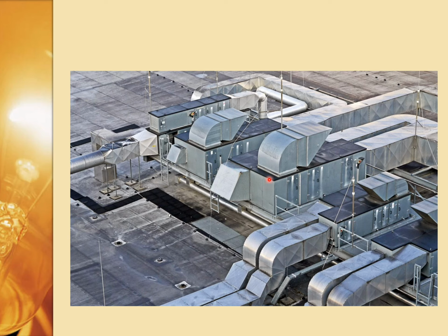So when you've got the economizer in these units open up and you're sucking in nothing but 100% outside air, you don't want to overpressurize the building. So you've got these big hoods, that's relief air. If you happen to be standing by one of these things when the economizer is open 100%, yeah, there's a lot of air moving out of here. The return is just through there.